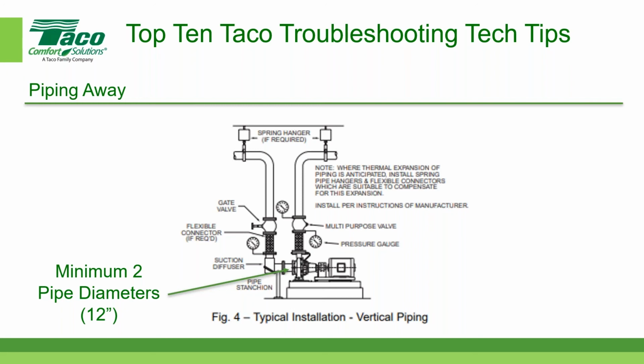If it's brand new pipe, you can assume the surface is probably pretty close to what the manufacturer is publishing. But if the pipe has been hanging around for 10, 20 years, especially if it's something like condenser water, the inside surface of that pipe could be very, very rough. If you don't take that into consideration, you'll get false readings with your ultrasonic flow meter.